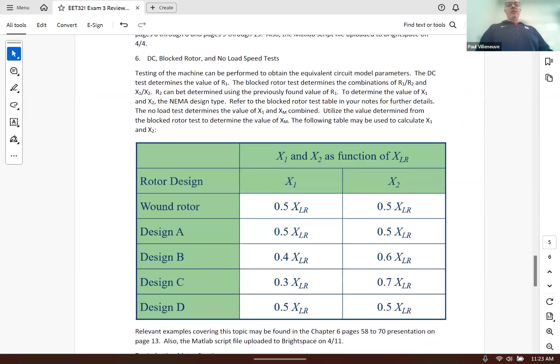That's why we use lock rotor test ratios based on the type of induction motor. If it's NEMA Design B, X1 is about 0.4 of the lock rotor reactance, and X2 is about 0.6. As we saw in lab, it's really hard to get those curves, really hard to get those parameters, but we can certainly run our tests.